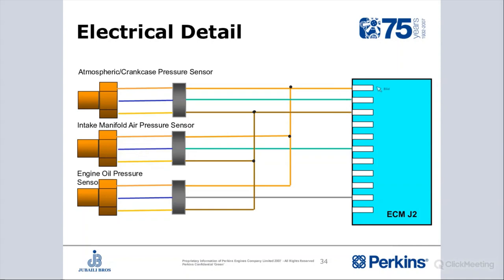Three wires are connected. This is a signal wire through which a 5-volt DC signal is sent from the ECM to the sensor. We have a ground wire. And we have this wire as well, through which a returning signal goes back to the ECM. The returning signal should be between 0.5 and 4.5 volts DC. If the returning signal is less than 0.5 or more than 4.5, a warning or shutdown will be generated on the ECM side, saying your sensor is shorted high or low.